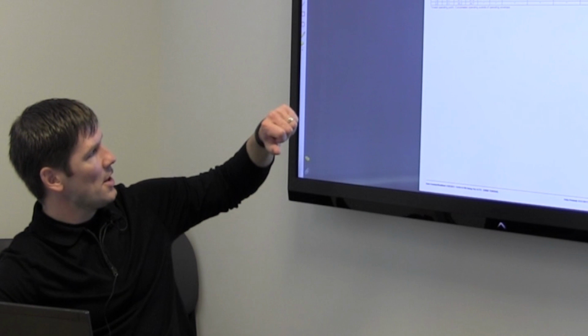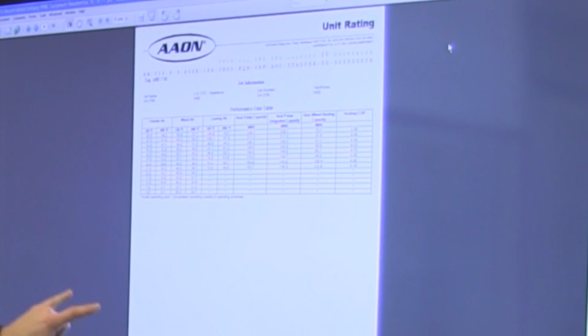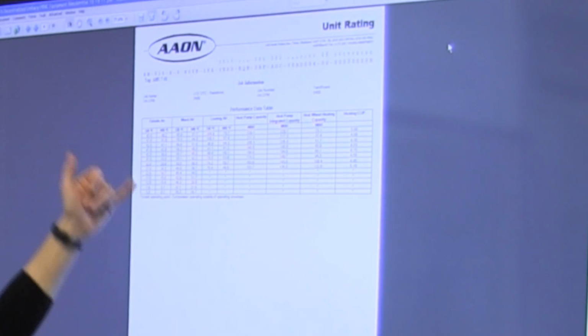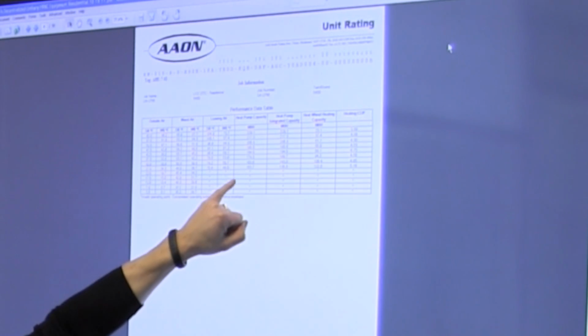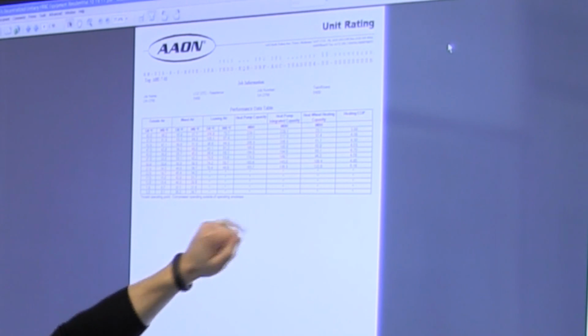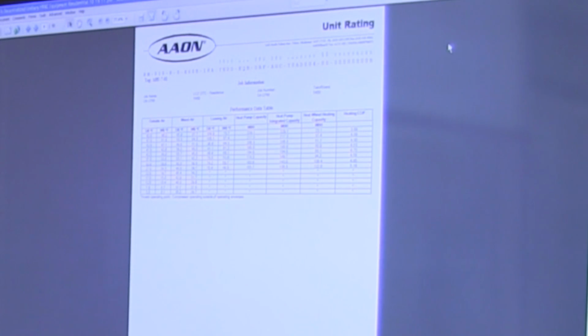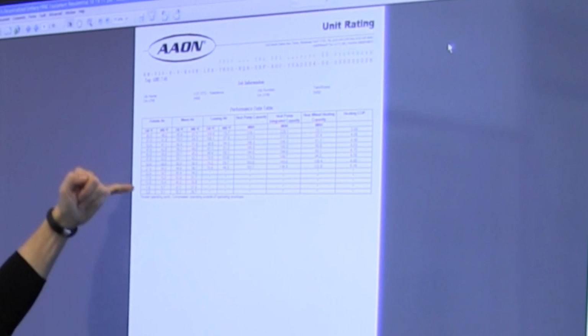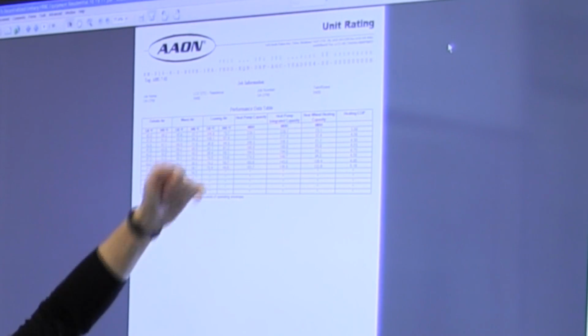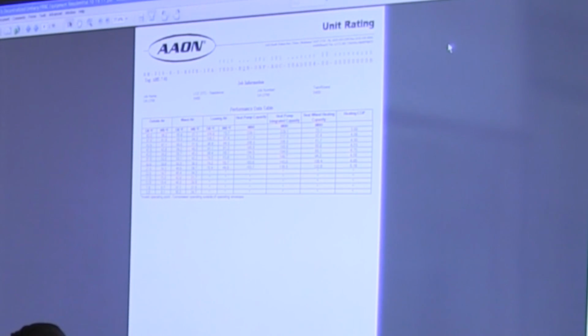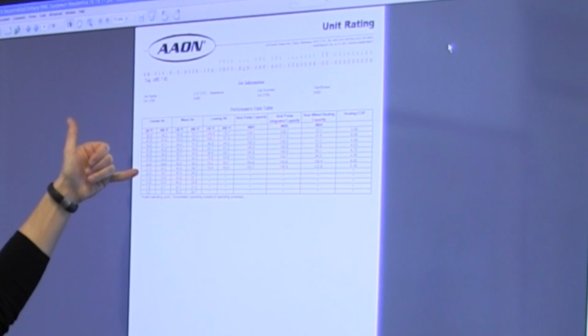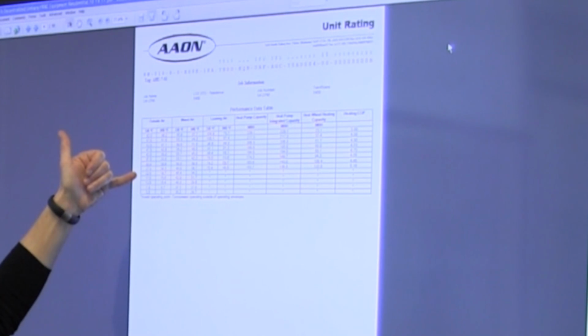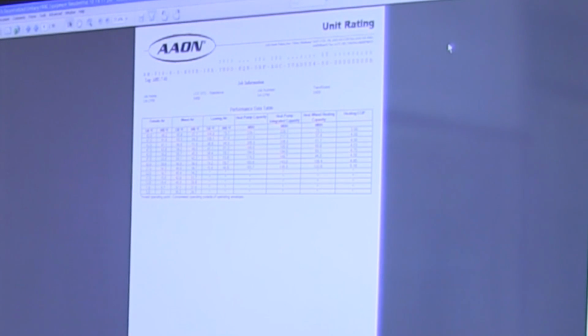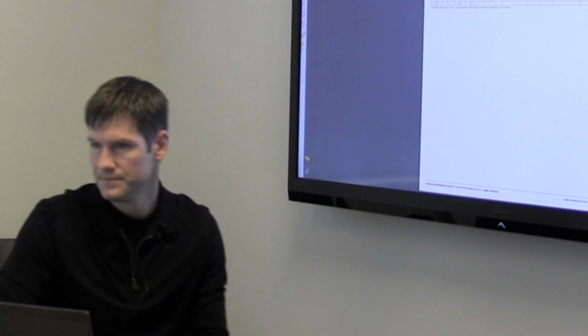This is an important chart on each of these. It shows you the heat pump performance subject to outside air temperature. So here we have outside air temperature, and here we have how much heat pump capacity you're going to get with that outside air temperature. With a heat pump, you can only harvest so much heat out of the outside air, right? So when this thing's in heating mode, as the outside air gets colder, you get less heat pump heat. And so you would then start using more and more electric heat to supplement that. And then at a particular cutoff, here at 27 degrees, below 27, the refrigerant pressures are too low to operate, and therefore you're only going to use electric heat.